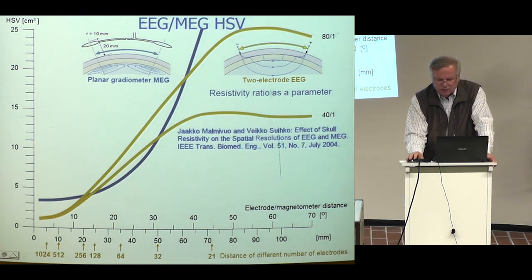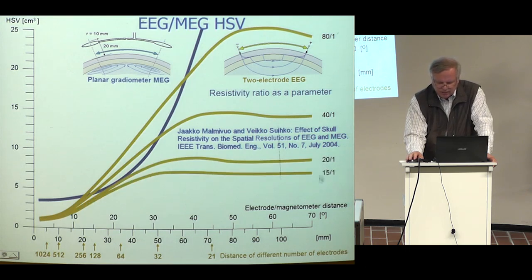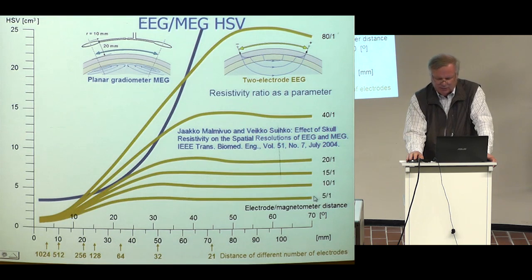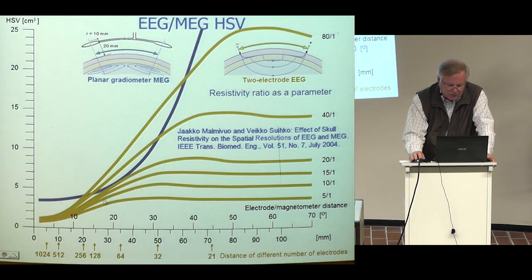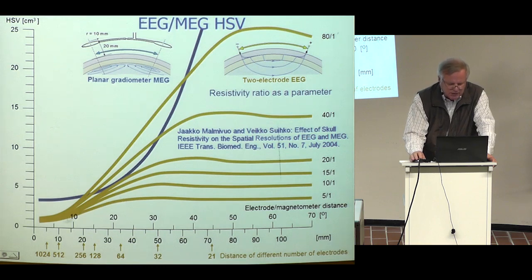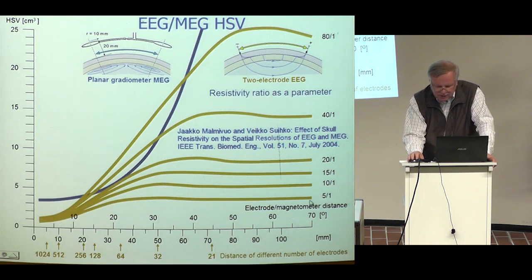Magnifying further: here is MEG planar gradiometer spatial resolution, and here is EEG with 15-to-1 and EEG with 5-to-1. EEG is clearly better. Here are the electrode distances in real cases: 128 electrodes equally spaced, 256 electrodes, 512 electrodes, and 1000 electrodes. You see that EEG has clearly better spatial resolution than MEG. This is the truth, but not the whole truth — the magnetometer coil can be made smaller, from 10 to 1 mm, and even placed closer to the scalp.